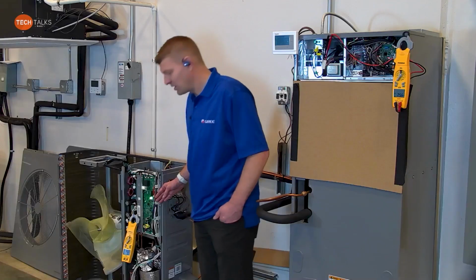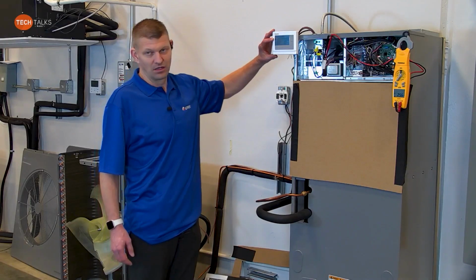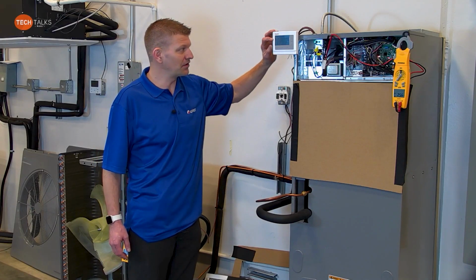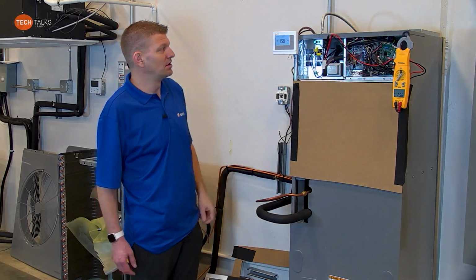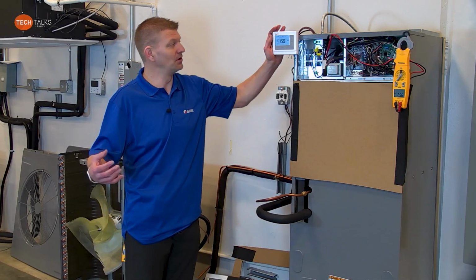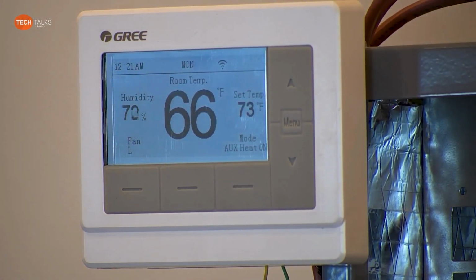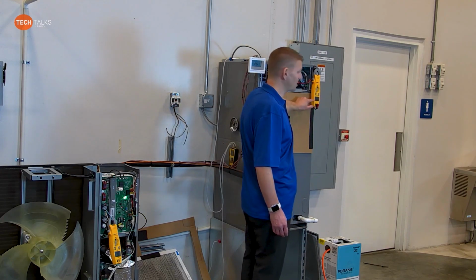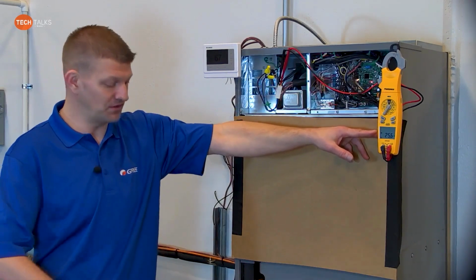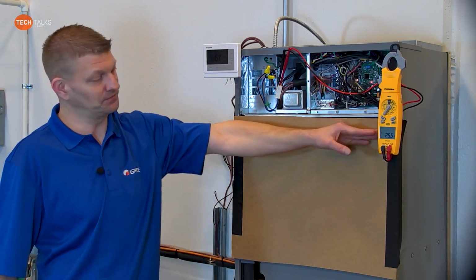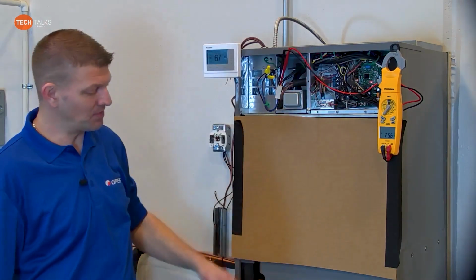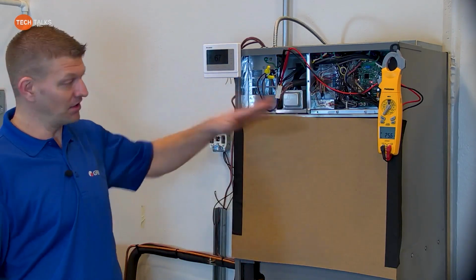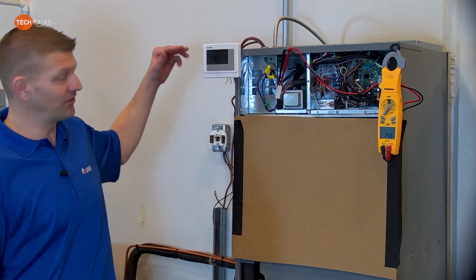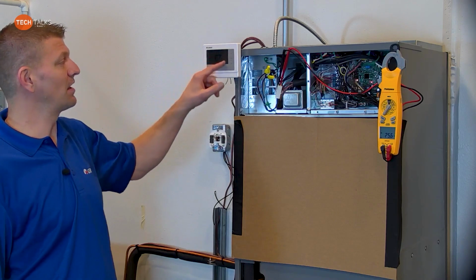Right. So, anyway. The EA code went away on this unit over here. It's staying on. And then as you can see up here, our GREE controller is still in refrigerant detection error. So we just hit a button here, that code goes away. That lets us know, when the homeowner comes back home, that we did have a leak, so they need to call a service tech. But just pushed a button, that went away. We are actually calling for auxiliary heat. We're still in auxiliary heat mode. As you can see, we have 25 volts right here. So it did what it was supposed to do. As soon as that sensor detected leak, it shut off 25 volts. The blower went to full speed. After the level dissipated enough for the sensor to reset, the 25 volts came back to the auxiliary heat, and all we had was the refrigerant leak detection on the controller.